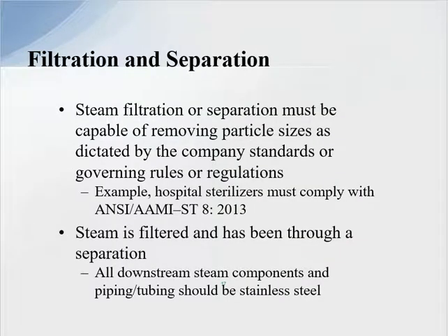Steam filtration or separation must be capable of removing particle size as dictated by company standards or governing rules or regulations. For example, hospital sterilizers must comply with ANSI/AAMI ST. Steam is filtered and has been through a separation. All downstream steam components and piping or tubing should be stainless steel. That's a best practice when we do filtration and separation.